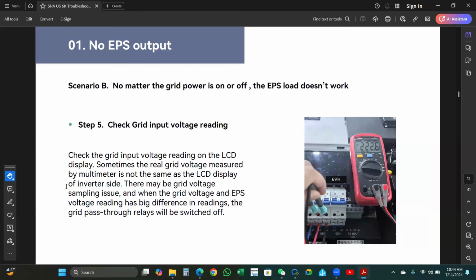Step five, check the grid input voltage reading. Check the grid input voltage reading on the LCD display. Sometimes the real grid voltage measured by a multimeter is not the same as the LCD display of the inverter side. There may be a grid voltage sampling issue. And when the grid voltage and EPS voltage readings have a big difference, the grid pass-through relays will be switched off. This is how you check with the integrated breaker.